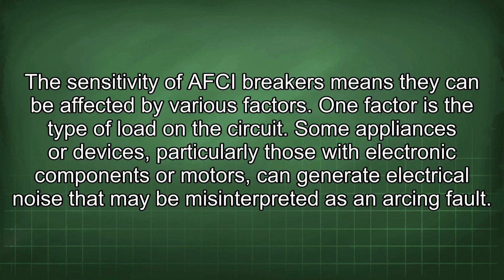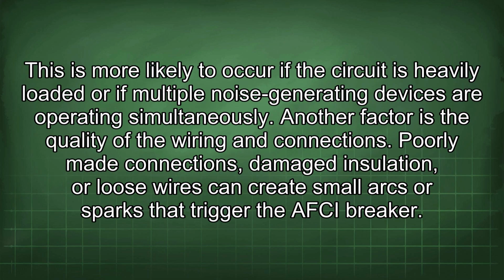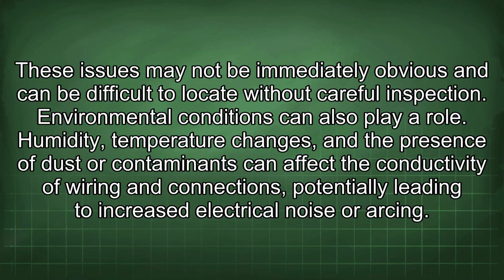Some appliances or devices, particularly those with electronic components or motors, can generate electrical noise that may be misinterpreted as an arcing fault. This is more likely to occur if the circuit is heavily loaded or if multiple noise-generating devices are operating simultaneously. Another factor is the quality of the wiring and connections. Poorly made connections, damaged insulation, or loose wires can create small arcs or sparks that trigger the AFCI breaker. These issues may not be immediately obvious and can be difficult to locate without careful inspection.